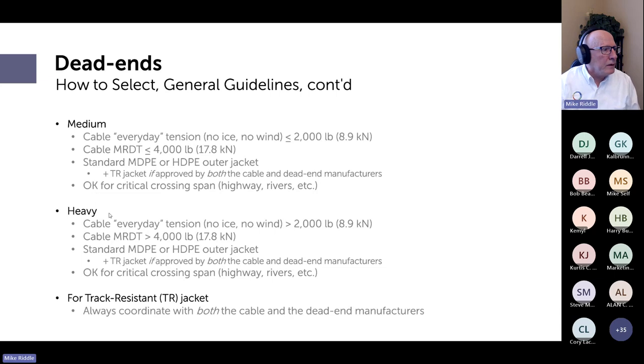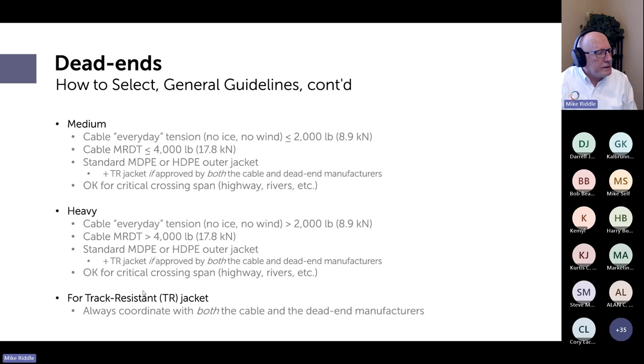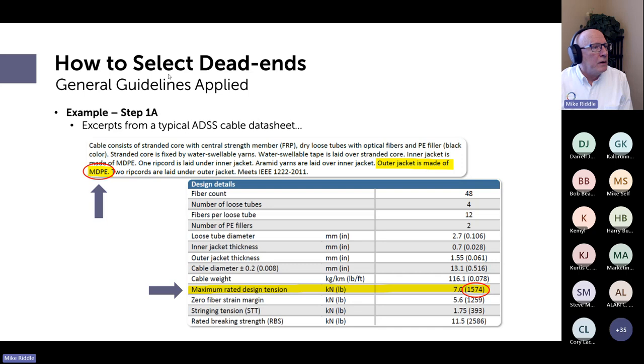Heavy duty dead ends: cable everyday tension greater than 2,000 pounds (no ice or wind), MRDT above 4,000 pounds, MDPE or HDPE jacket, tracking resistant okay if approved by both manufacturers, and also acceptable for critical crossing spans. A heavy duty dead end is generally a special design — you're in unusual territory at these conditions.